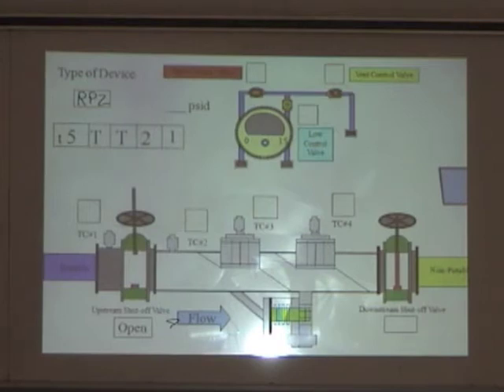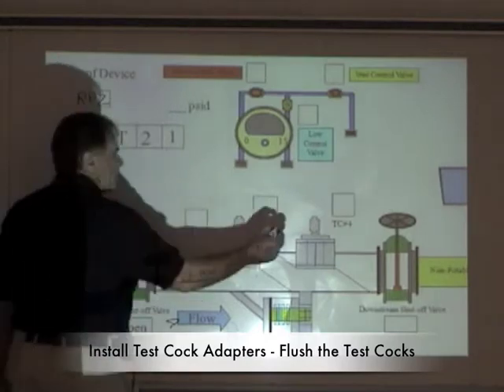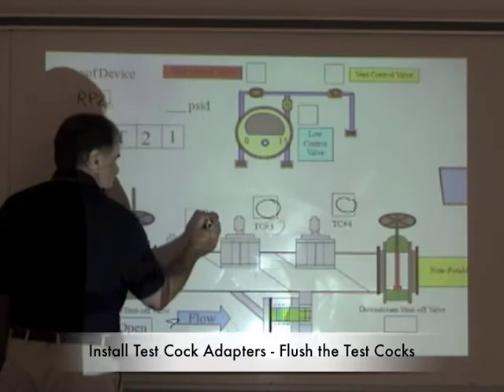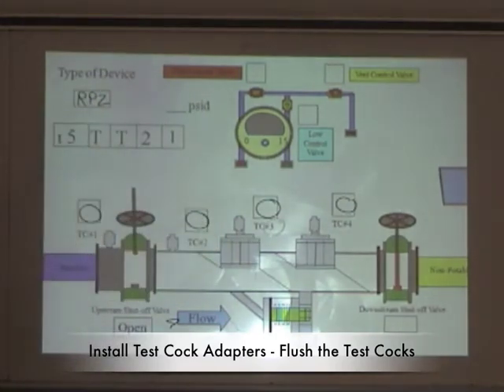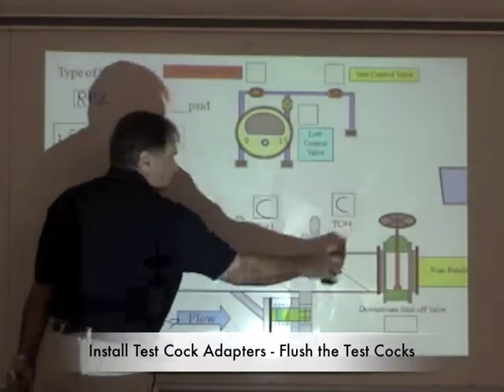We need to install our adapters and flush. We install our adapters and flush by opening up test cock number four, then test cock number three, test cock number two, test cock number one. Then we close test cock number one, test cock number two, test cock number three, and test cock number four.